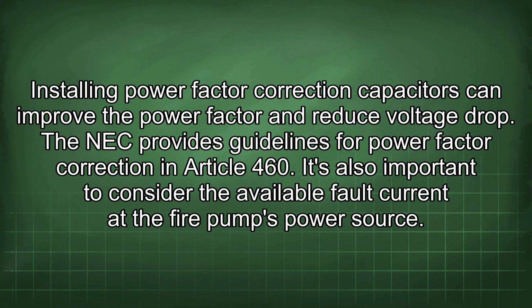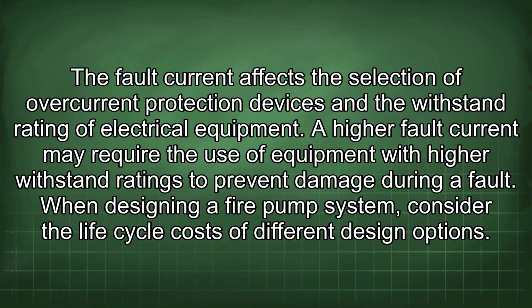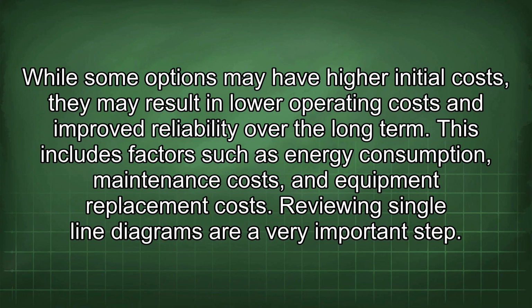It's also important to consider the available fault current at the fire pump's power source. The fault current affects the selection of overcurrent protection devices and the withstand rating of electrical equipment. A higher fault current may require the use of equipment with higher withstand ratings to prevent damage during a fault. When designing a fire pump system, consider the life cycle costs of different design options. While some options may have higher initial costs, they may result in lower operating costs and improved reliability over the long term. This includes factors such as energy consumption, maintenance costs, and equipment replacement costs.